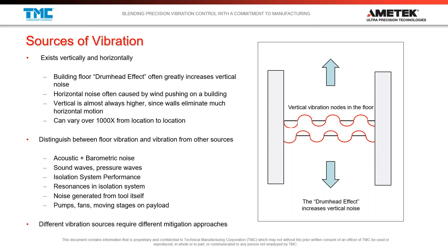You also have to be careful when you're thinking about floor vibration. You've got to be able to distinguish between floor vibration and vibration from other sources. There are a lot of sources, such as acoustic and barometric, which affect not only the system by pushing on it, but can also affect the isolators if there are isolators. Sound waves, pressure waves, things like that. Your own system is going to have its own resonances, and I'll talk about resonances in later slides. But you also have to be careful about payload noise.